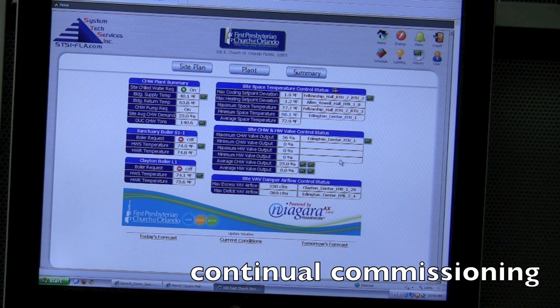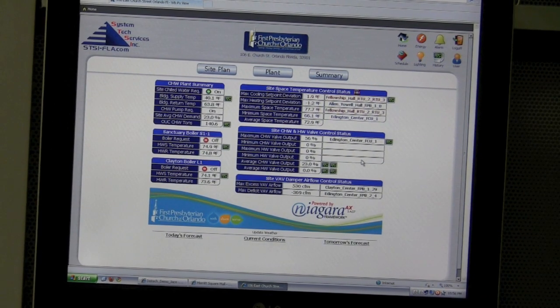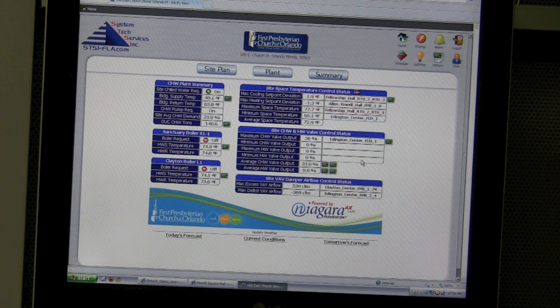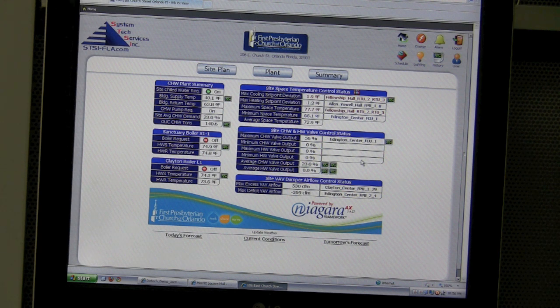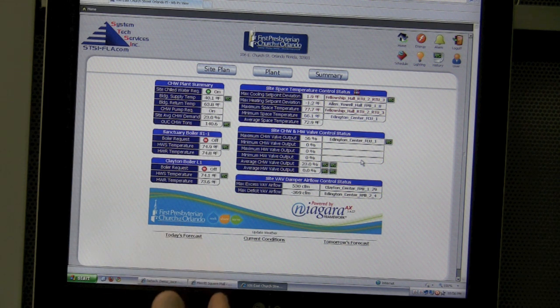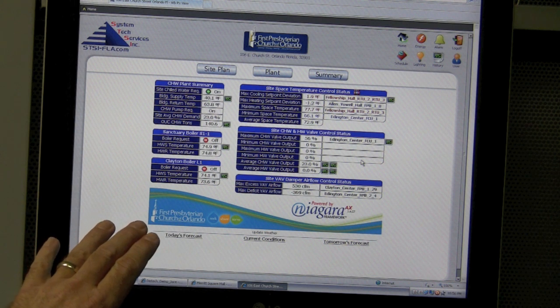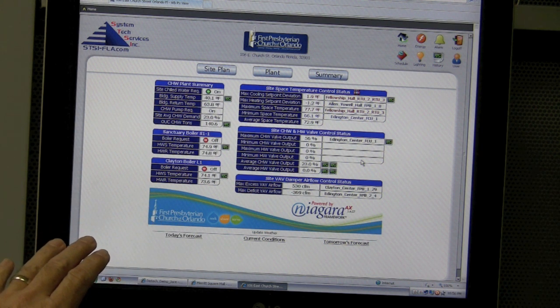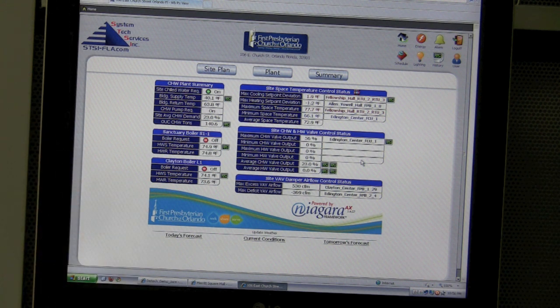We do something called continual commissioning. We write software that's like a report card for the building — we can see who's performing and who's within design. Once a customer works with us and we put this in, he's set. As long as the building is there, he's getting constant commissioning, which has a huge impact on long-term energy savings. We put the pertinent information right on the home page — they come in and see a five-degree deviation or a valve that's suddenly at 100% that wasn't before. That's a flag to go check it out. It's a benefit for both sides — it's just an added value they get with the system.